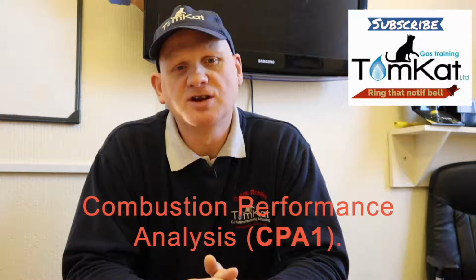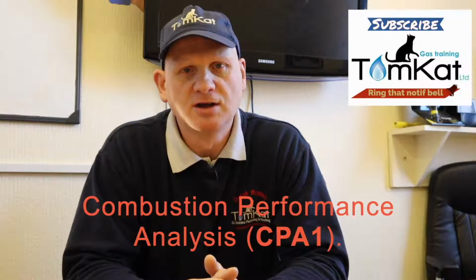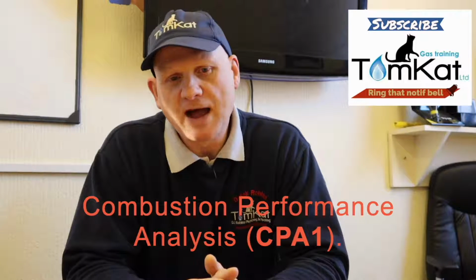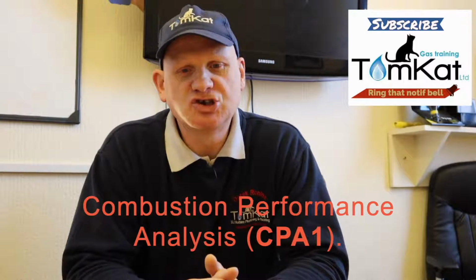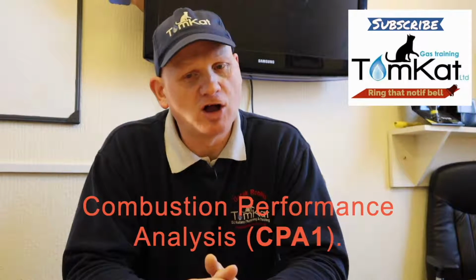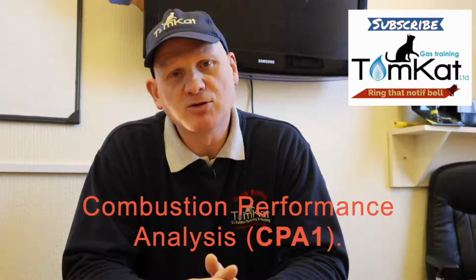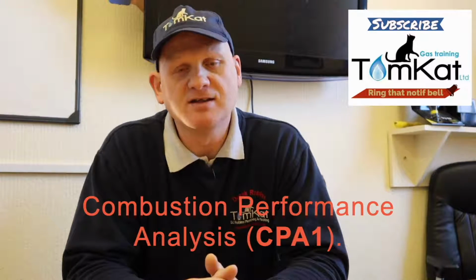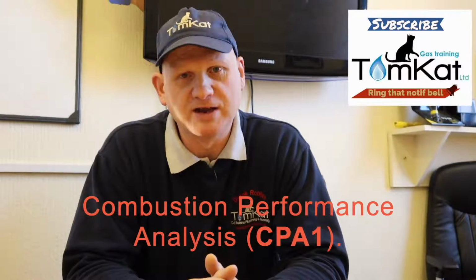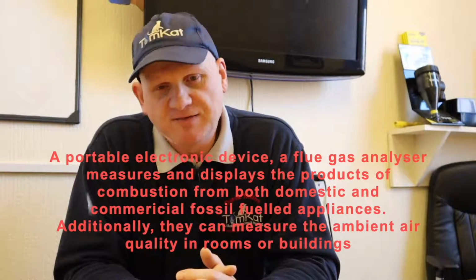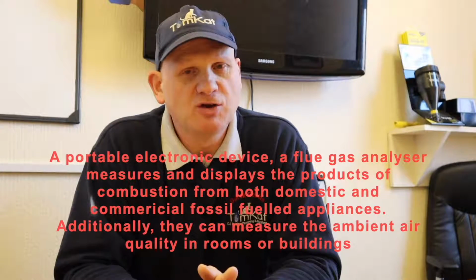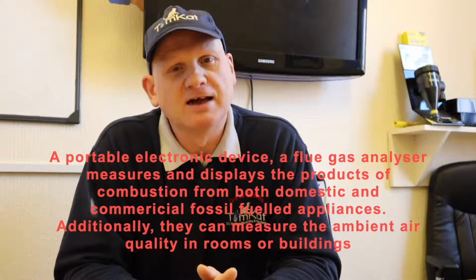From the 1st of Jan 2012, gas engineers have needed the qualification CPA1. What that means is they must be able to check the combustion products of all gas appliances and be able to understand these readings and be able to act upon the readings they are getting. To help the gas engineer achieve this, they must be able to use and understand a flue gas analyser.